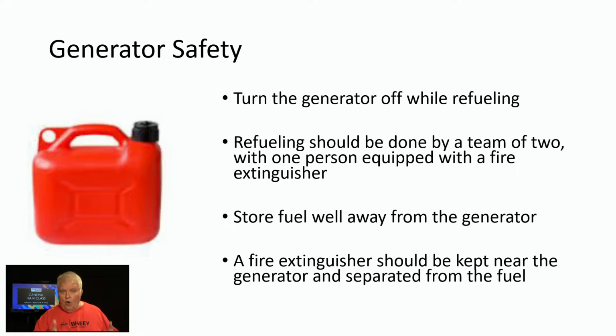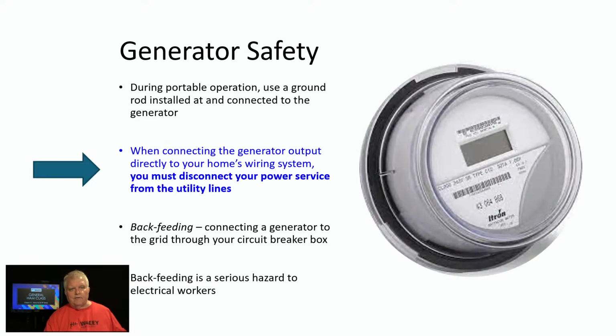If you're going to be powering your home during an emergency, like we had Hurricane Helene come through here, the upstate of South Carolina, if you're going to power your house, make sure that you're disconnected from your utility power lines. One way to do that is actually to pull the meter out of its socket on the outside of your house. That will physically disconnect your house from the lines. You do not want to connect a generator up to your house wiring while still connected to the lines, because you can backfeed the lines and you could injure a lineman. So that's not anything that you want to do. So just keep that in mind.